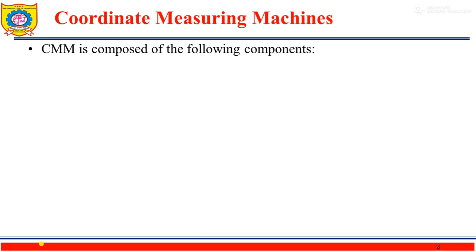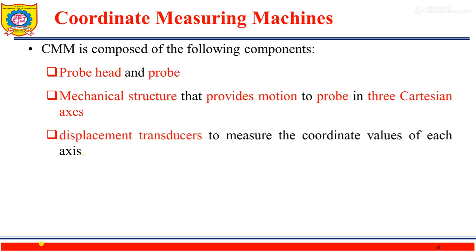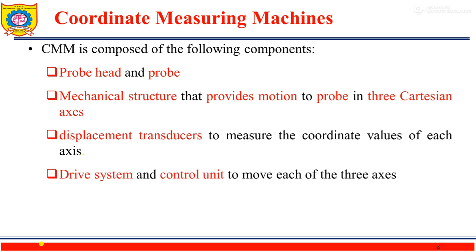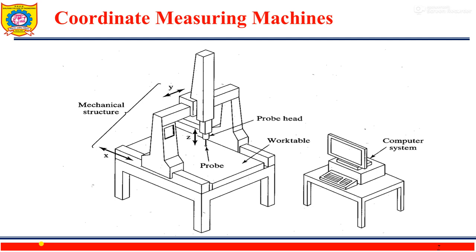Let us study the CMM construction. A CMM is composed of the following components: probe head and probe; a mechanical structure that provides motion to the probe along three Cartesian axes; displacement transducers to measure the coordinate values of each axis; and a drive system and control unit to move each of the three axes. The work table is horizontal, mostly in the XY plane.